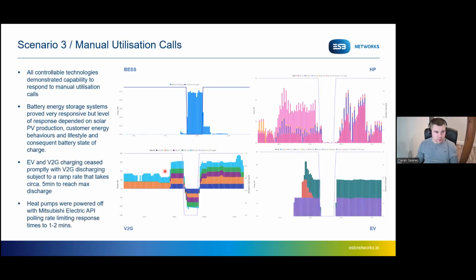In terms of some of the outputs then, from the battery system, we can see when we get the command to go from 1 to 0 here, then the battery systems go to basically full discharge for the duration of the test, and then revert back to their previous mode of operation, whatever the optimization scheme had scheduled for that particular day. Similarly, on the top right, we have the heat pumps. There is a little bit of a lag with the turning off and turning on of the heat pump, mainly due to the data sampling of the API that we were leveraging from Mitsubishi Electric.